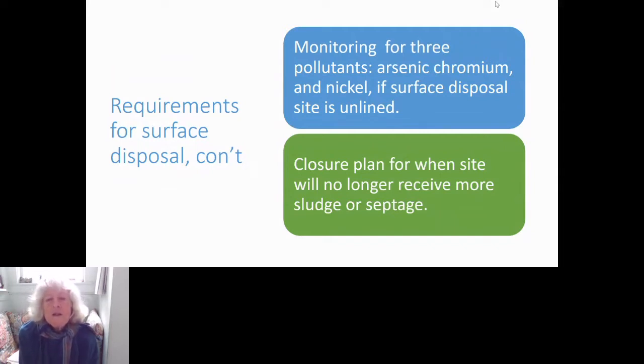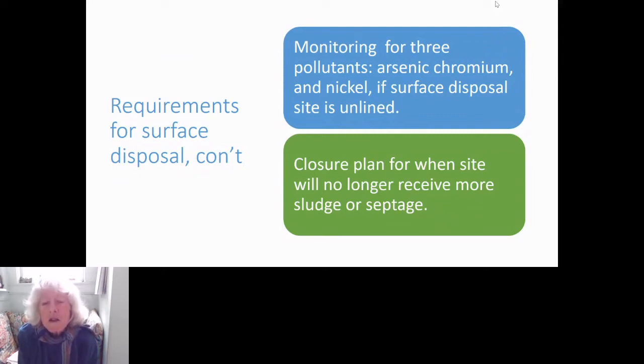If you have a surface disposal site where you're permanently disposing of sludge, there's a requirement to monitor for three pollutants — arsenic, chromium, and nickel — if the site is unlined. If the site is lined with tarps or similar, you don't need to monitor for those. This only applies to sludge from a treatment plant, not to domestic septage. You also need to prepare a closure plan when you're done adding sludge to the site.